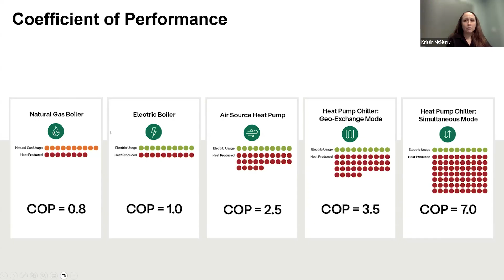There's a helpful diagram that you helped create that really visualizes that - can you walk us through this? The orange dots or green dots are the fuel we put in, which might mean electrical power, and the red dots are the heat we produce or move. Something like a natural gas boiler, which has an efficiency of 80%, has a COP of 0.8. An electric boiler at 100% or maybe 99% efficiency gets a COP of 1. But when you get into technologies where you're moving heat from one system to another, that's where you get COPs greater than 1 - and that's what we'll talk about next time with low temperature hot water.